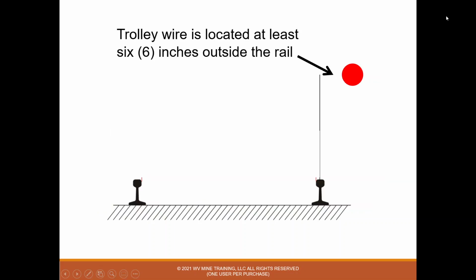And here we have a little picture showing, if you can see my pointer, the rail here, and just imagine we project a line straight up to the roof, and at that point the trolley wire, which is the red ball, would be located at least 6 inches outside the track gauge. And again, if you can see my pointer floating around here, the equipment operator would be inside that somewhere, so he's never going to come into contact with the trolley wire.